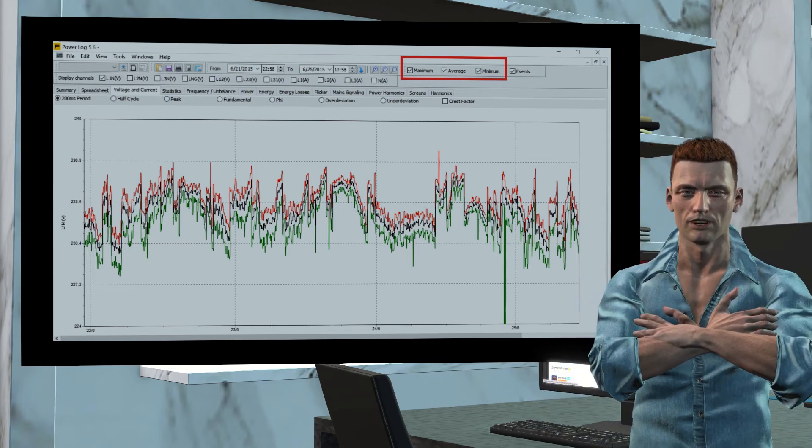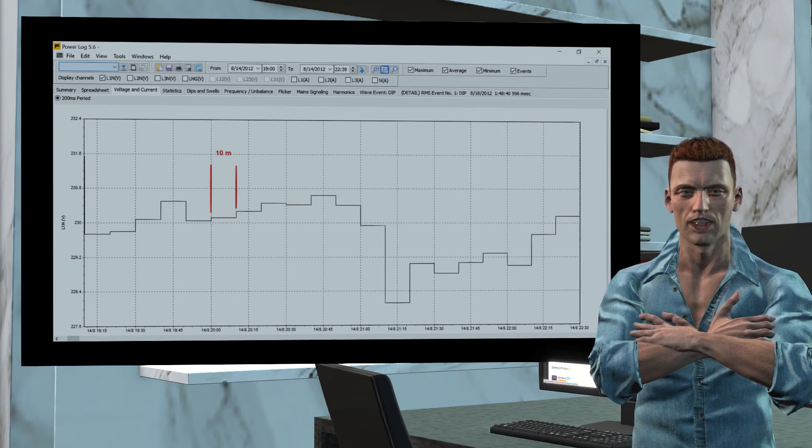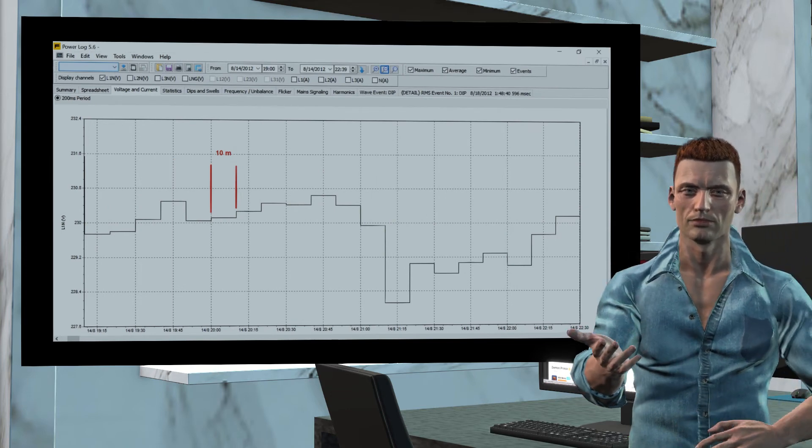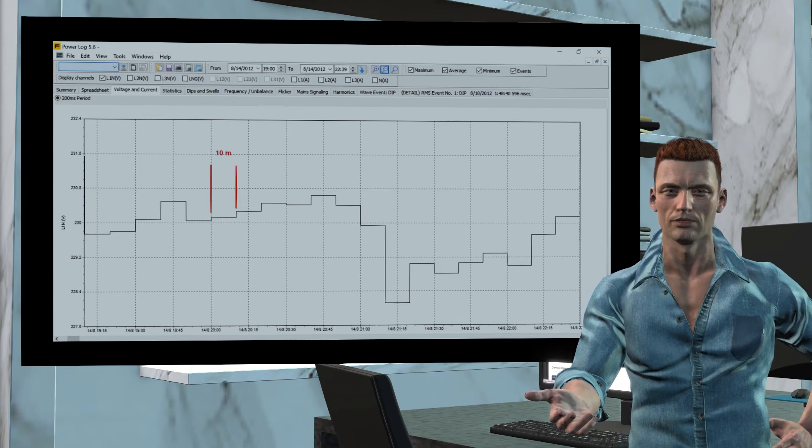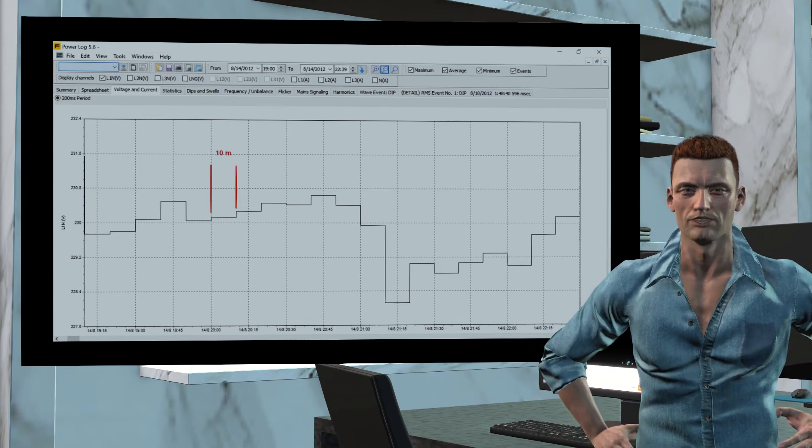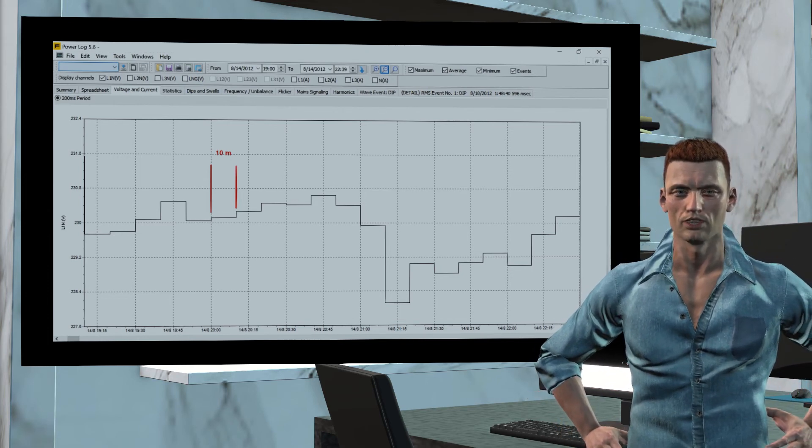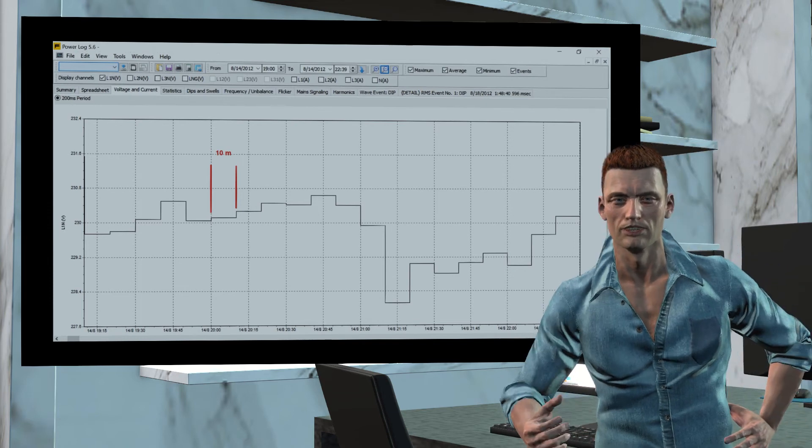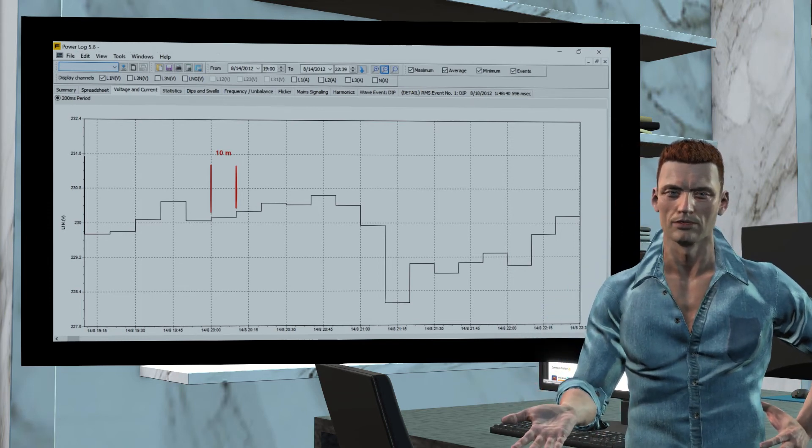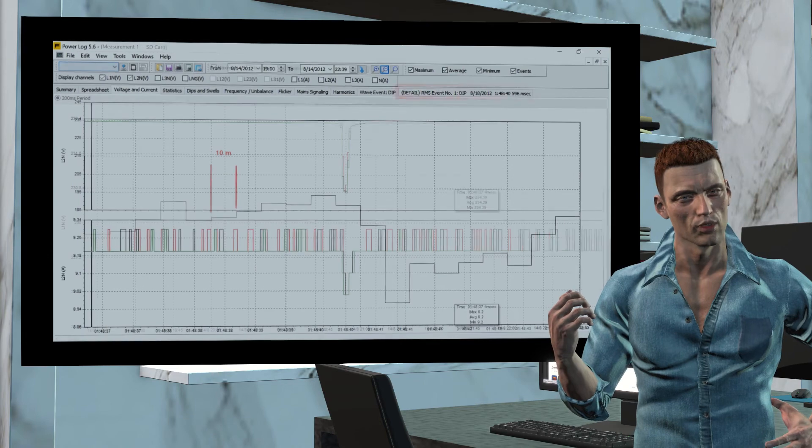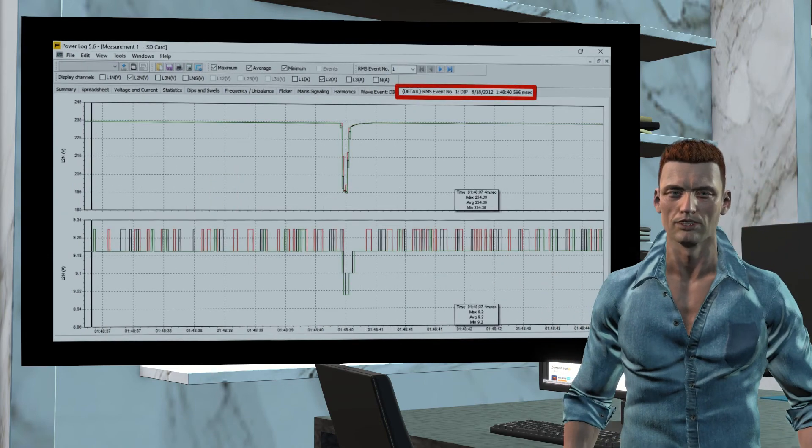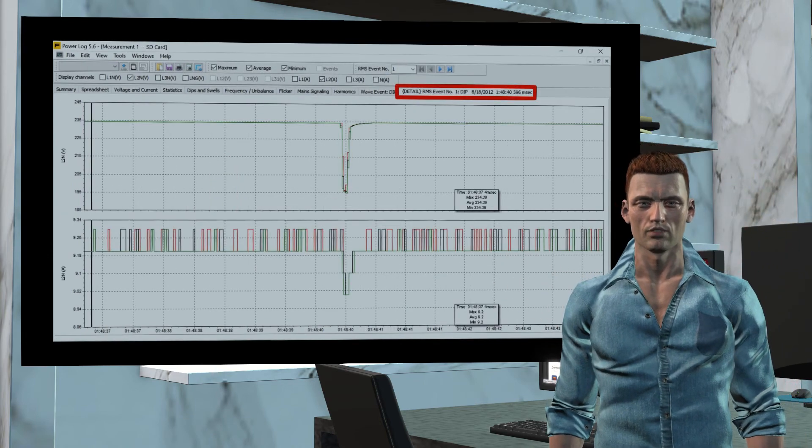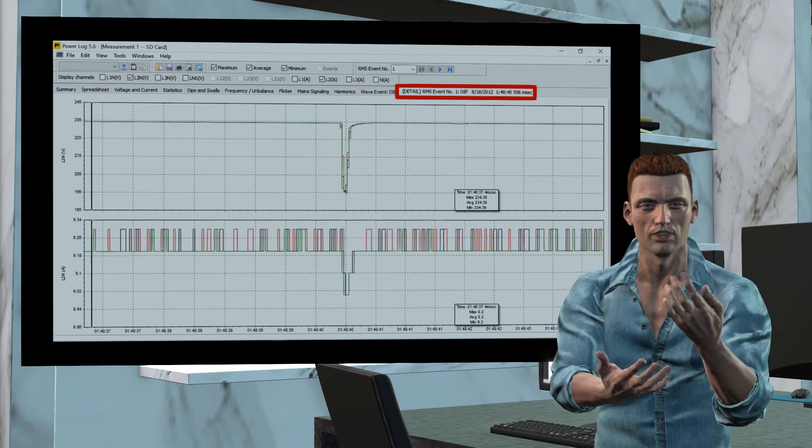If we make a record according to the European standard EN 50160, for which the aggregation interval should be 10 minutes, if we zoom in until a trend graph is enlarged enough, we will see that voltage changes occur, precisely, every 10 minutes. In case the analyzer does not detect any anomaly in the network, the selected aggregation interval will give us the temporal resolution between the values of the trend graphs.